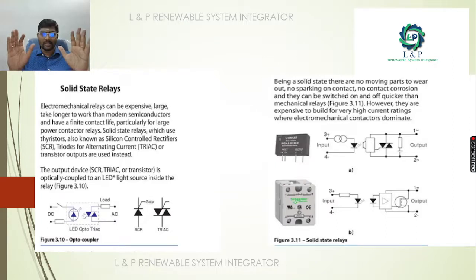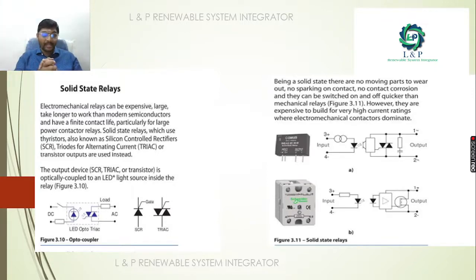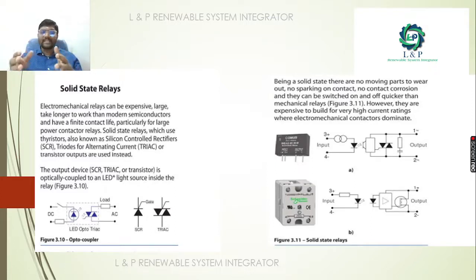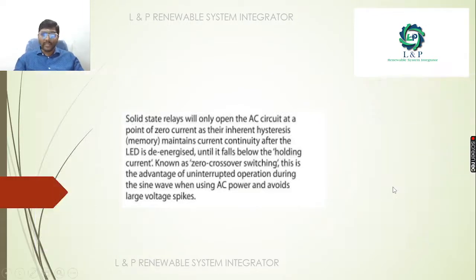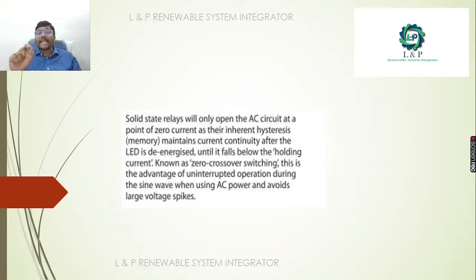Solid state relays are electronic alternatives to electromagnetic relays — they are more compact and faster. These solid state relays use thyristors such as SCRs (silicon controlled rectifiers) and TRIACs (triode for alternating current). The output devices — SCR, TRIAC, or transistor — are optically coupled to an LED. This solid state relay will only open the AC circuit at a point of zero current, known as zero crossing switching.